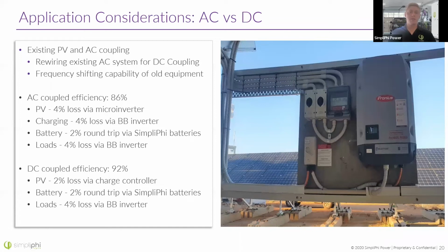All right, so existing PV and should you AC or DC couple? Rewiring an existing AC coupled system for DC coupling can be a lot of time and effort, and realistically, it's not often done. I would say that if you've already got an AC coupled system in there, the advantages may not outweigh the cost. As long as you're happy with the specs of your old system, I would say keep it in there. If you've got a brand new system, I would really say that the advantage of DC coupling is always the way to go for a brand new system in most cases.